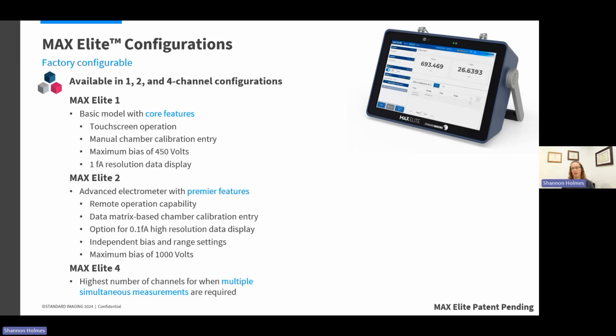So if you're using one of the larger spherical chambers for environmental measurements or a different detector that needs that high voltage, this is the electrometer that will be capable of providing that. The 4-channel electrometer has all those premier features as well, and really is useful if you're trying to do more than 2 simultaneous measurements. So a couple examples of where this would happen: this is our constancy check phantom.